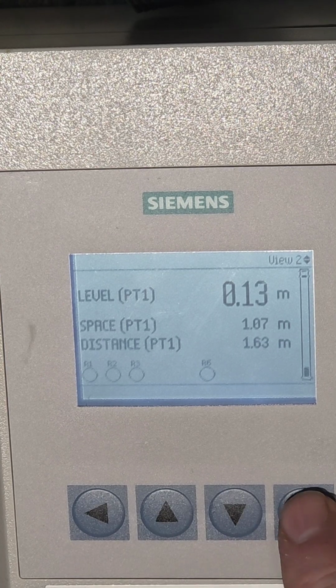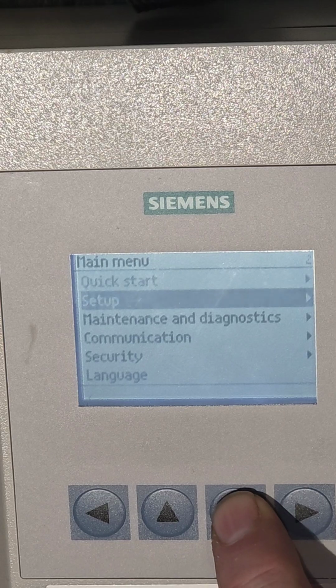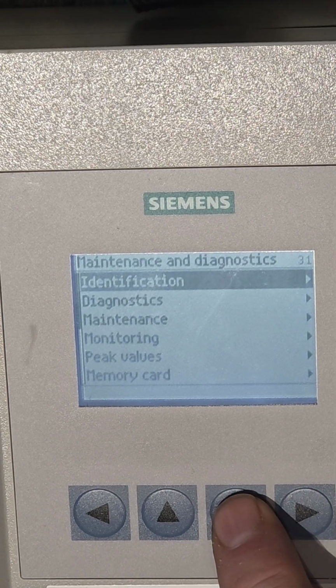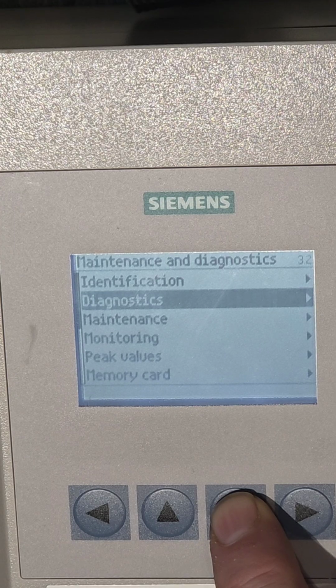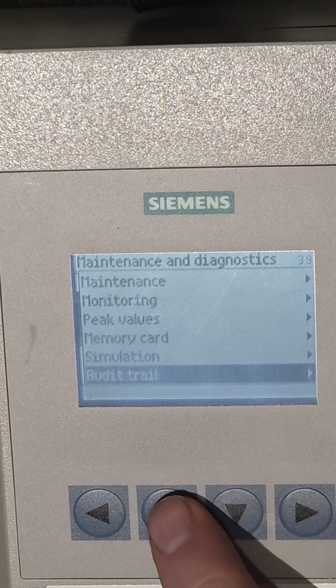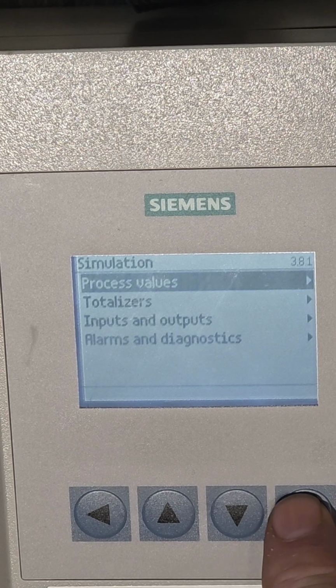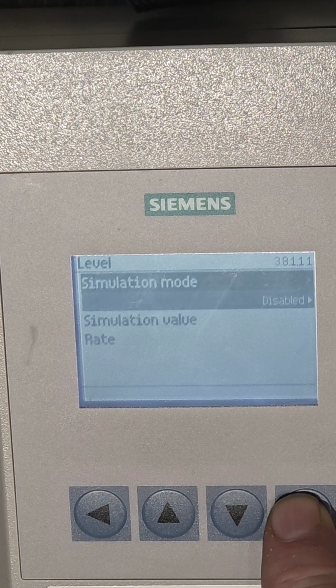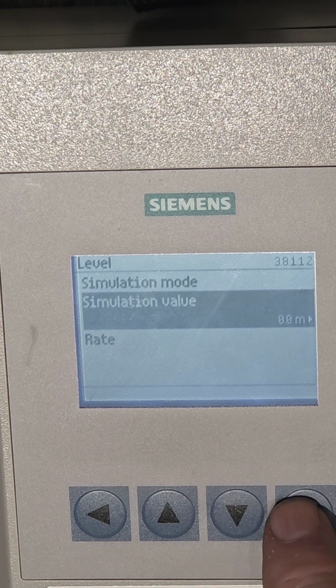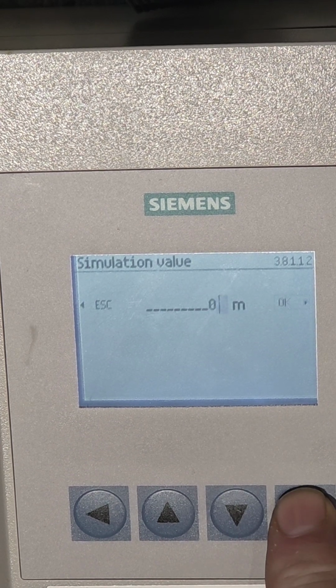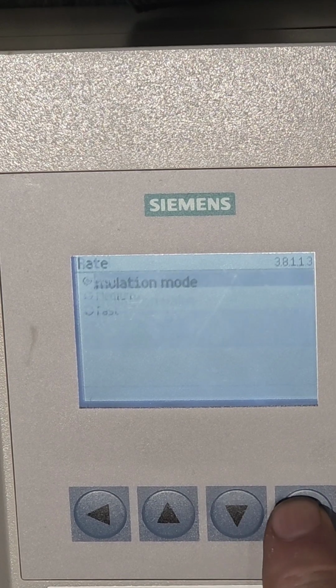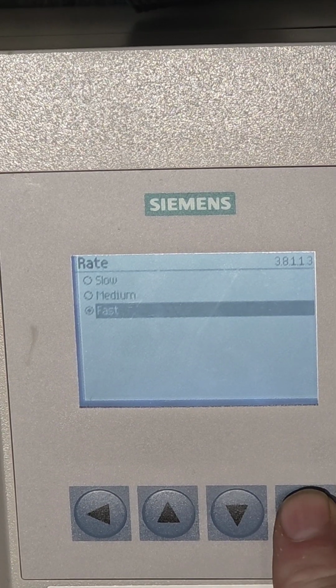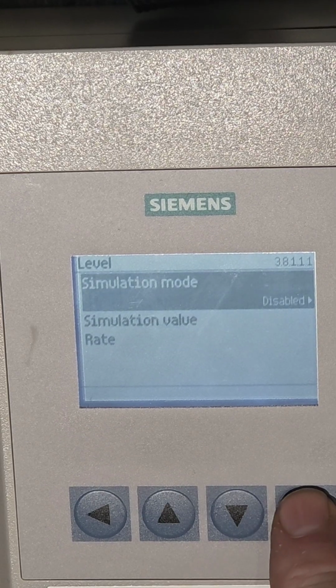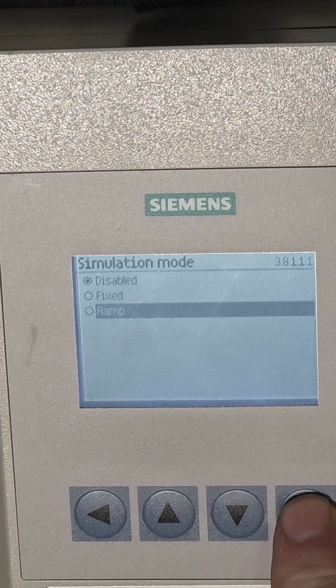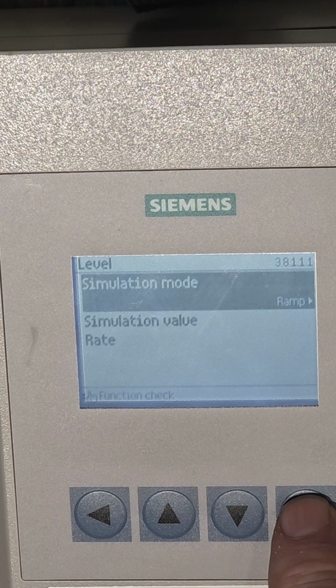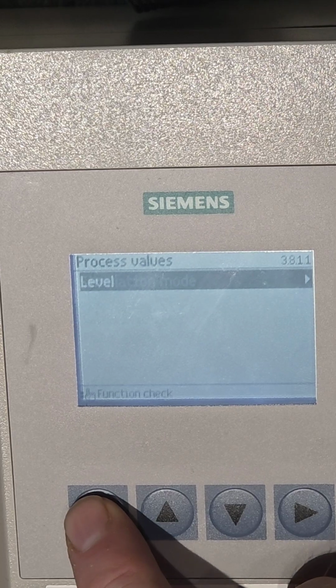Now to do a simulation, right click, maintenance and diagnostics, all the way down to simulation, right click, process values, level, come down to simulation value. I want that to start at 0 meters, that's okay. And the rate, I want to change that to fast, press once, press again, and then come up to simulation mode, change from disabled to ramp, press once to highlight, press again, it should now be ramping. And then you come right back out of the whole thing.